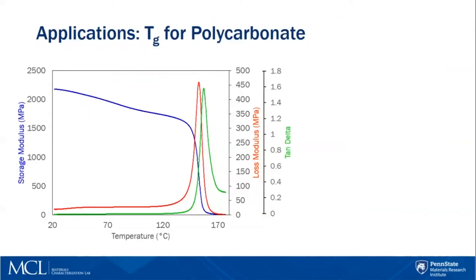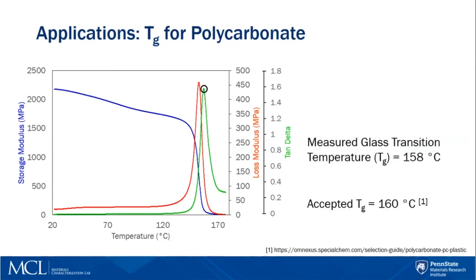Another example of mechanical characterization is shown here for determining the glass transition temperature for a polycarbonate material. This sample was tested on a dynamic mechanical analyzer, a DMA instrument. The specimen was oscillated between 0 and 10 percent strain as the temperature was increased. From this plot, we are able to analyze the loss modulus and the tan delta in order to determine the specific glass transition temperature for this material.